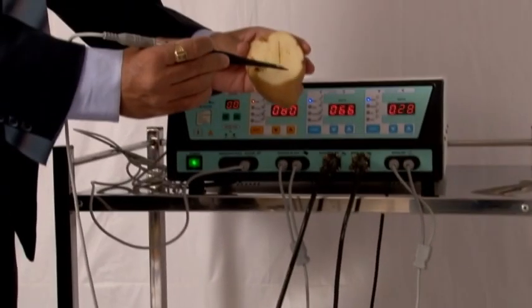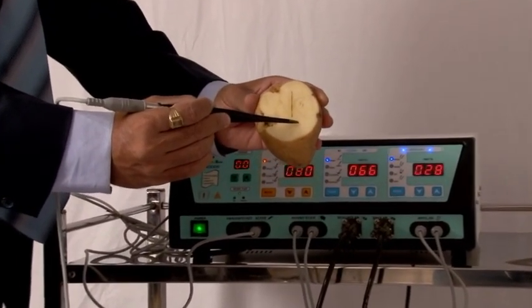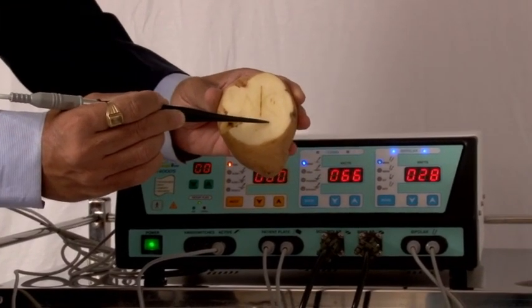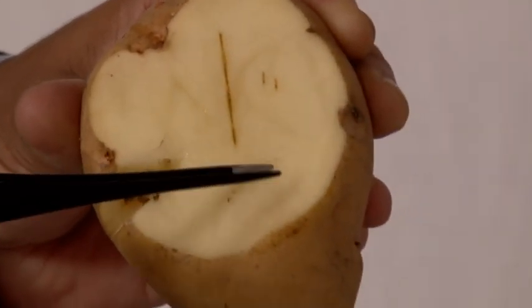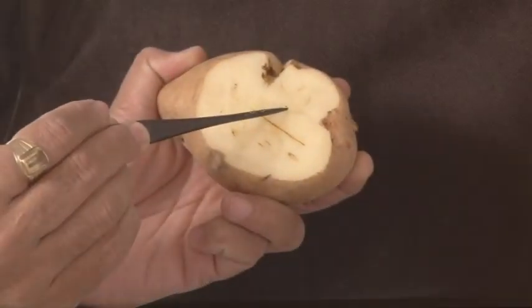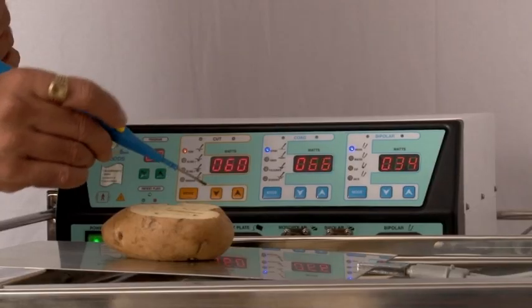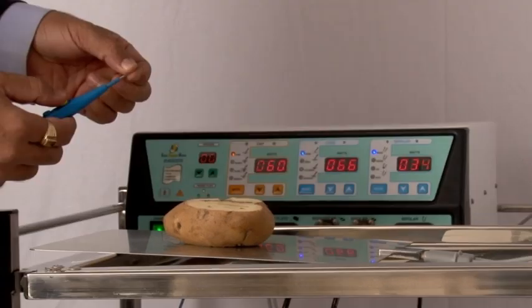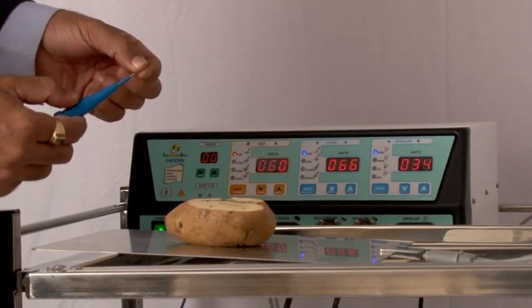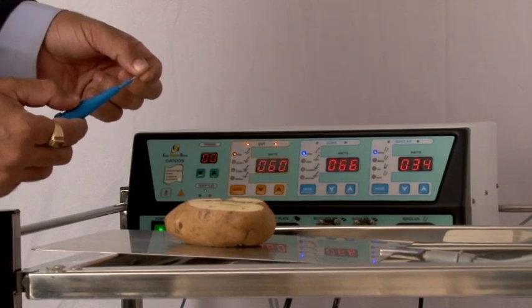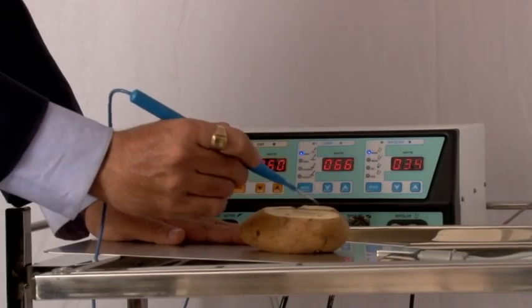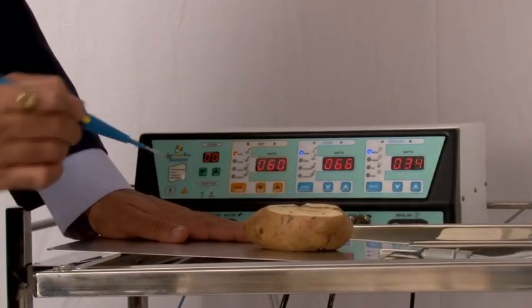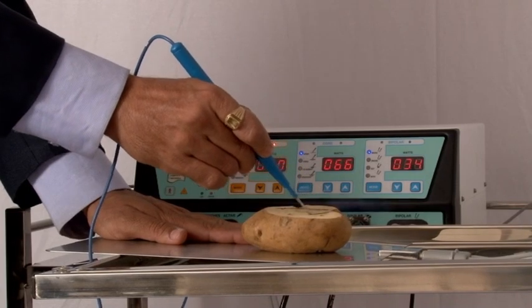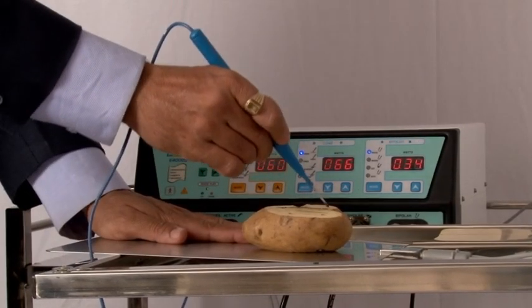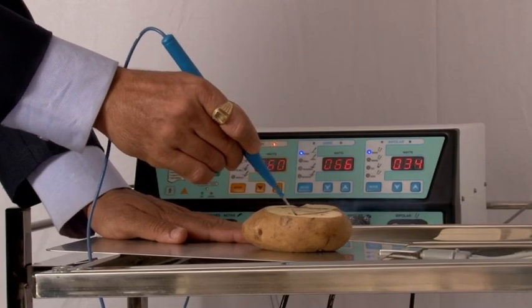A white colored coagulation effect without charring is the specialty of our electrosurgical generator. One can notice there is no sparking in this mode. This proves machine's control and precision in delivery of the current. Isolated design of the machine is so safe that it does not give any shock or neuromuscular stimulation even after touching the live electrode. Even the return electrode, a patient plate, is also safe that it does not give any shock or neuromuscular stimulation even after touching in live condition.